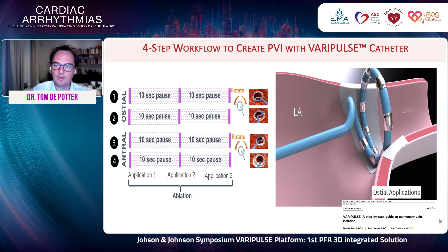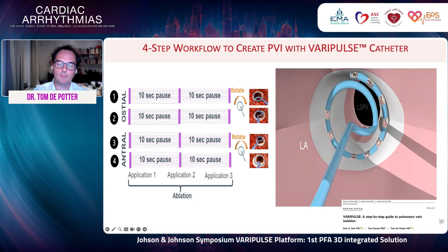The waiting time is 10 seconds between energy delivery, and this is done automatically in the generator. You don't have to do anything. You simply press start. The generator will give 3 pulses, wait 10 seconds in between every pulse, then you rotate the catheter and you deliver 3 more pulses. So as you have just seen in this animation, we have ablated 1 PV ostium and 1 PV antrum with this strategy.